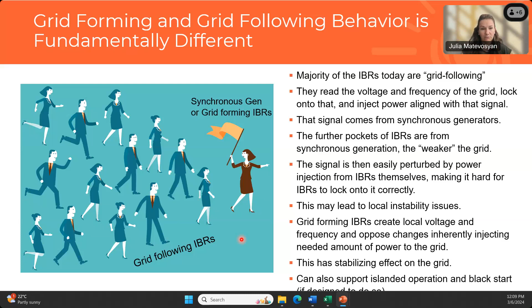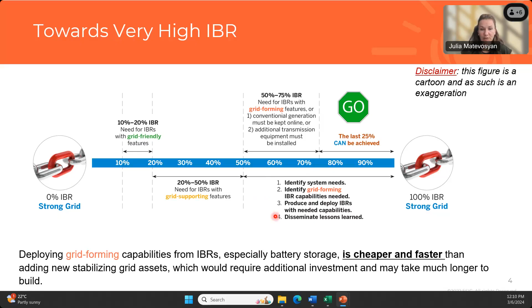So deploying this grid forming capability, so this advanced control capability in IBRs, especially in batteries, is cheaper and faster than adding new stabilizing grid assets. And the new stabilizing grid assets also require additional investments and take longer time to build. So what we need to do to kind of pass this threshold and achieve higher shares of inverter-based resources is identify what system actually needs, identify advanced controls or grid forming controls of inverter-based resources and what capabilities are needed, and then produce and deploy IBRs with needed capabilities and also disseminate lessons learned. So I think we're kind of finding ourselves between this second and fourth step here.